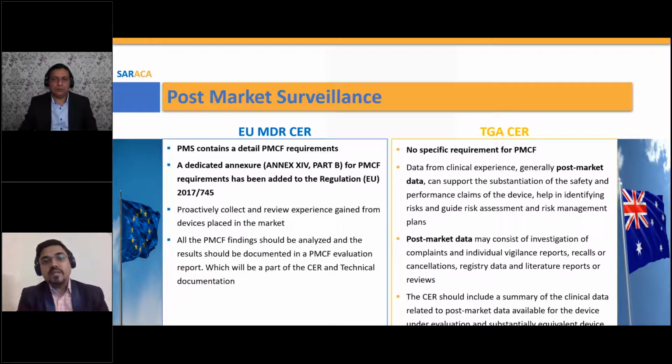But when it comes to MDR, earlier also I can tell you, in MDD and the directive, there is no very stringent requirement. It's not a very critical or stringent requirement for a PMCF. You need to have a PMCF, but there is no such stringent requirement in MDD. But now in MDR, this new regulation 2017-745, there is a dedicated section, a dedicated annexure, part of the annexure has been added, that is only for PMCF.